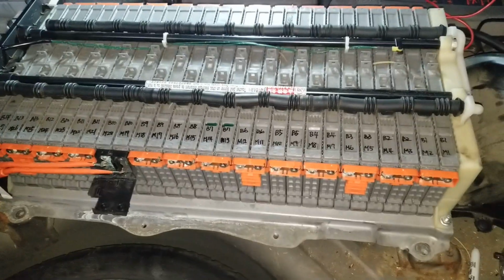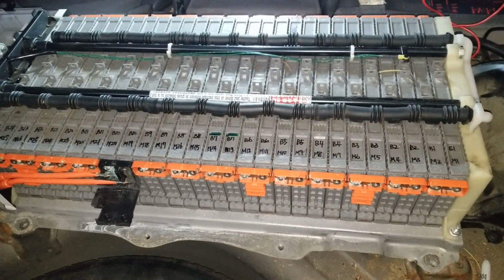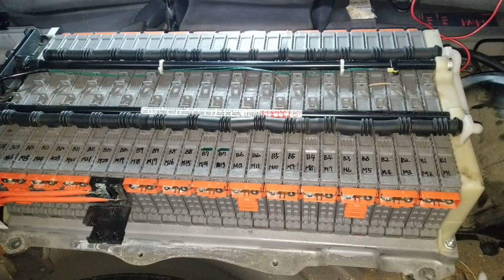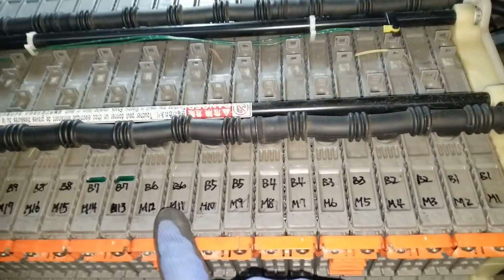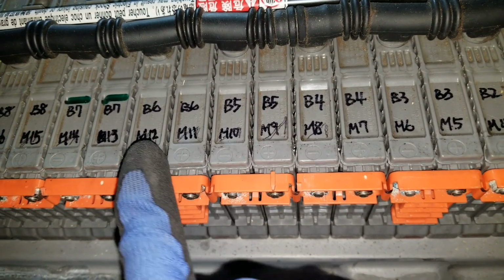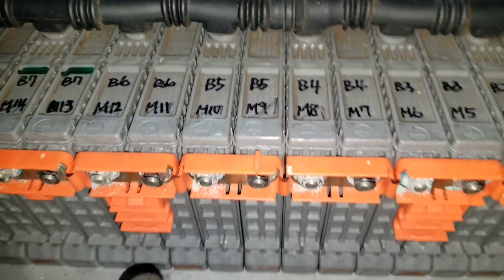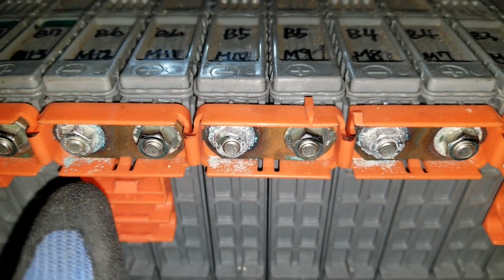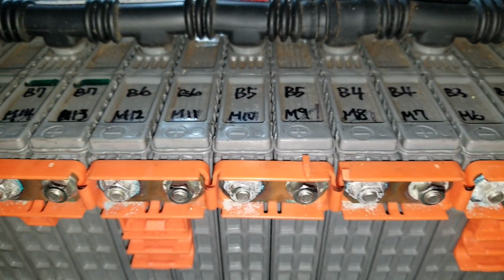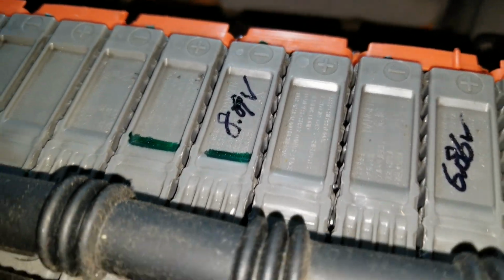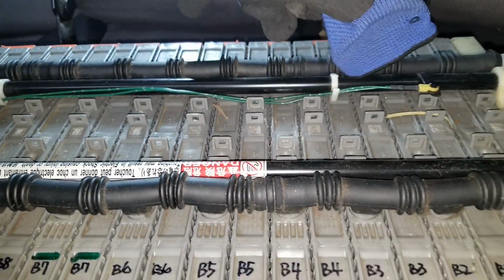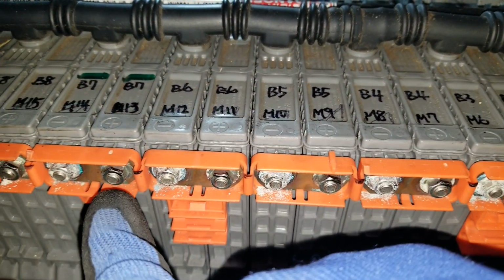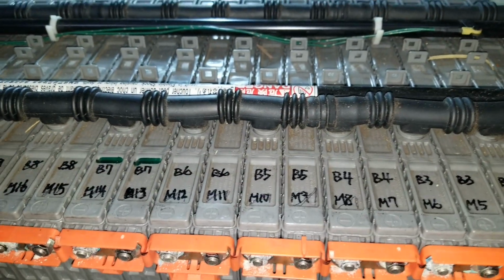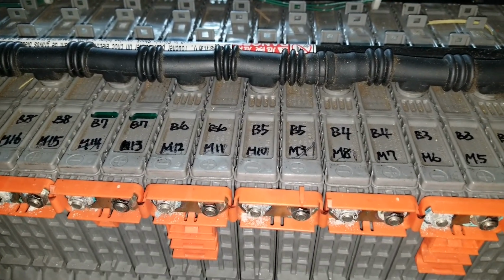Alright, so I measured all the modules. Most of them show like 8.1 volts, except the one with block 6 and module 12. When I measure from the bolt or post to the other post, it shows 8.09 volts. But when I measure through the bus bar to the bolt or post right here, it's fluctuating up and down.